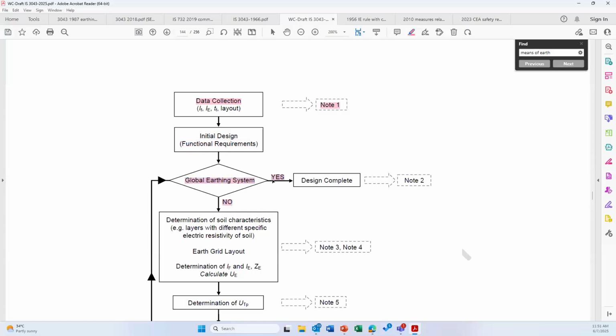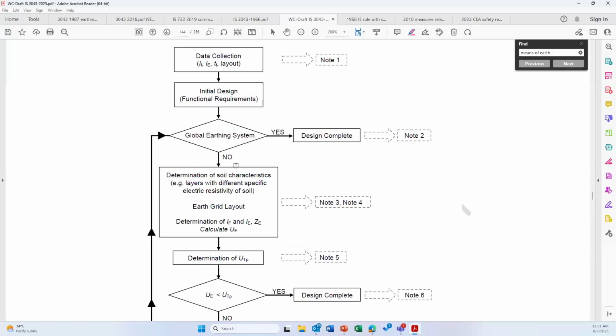Then we go to the global earthing system. Yes, design complete. Note 2. So if you are making a global earthing system, then your job is done. Very simple. What exactly is a global earthing system? I will show you in the definition. Now, a global earthing system is applicable for an electrical installation which is part of an 11 kV supply or 22, 33 kV or GIS 66, 110, whatever. If it is a part of a building or if it's a part of an industry. So no global earthing system.